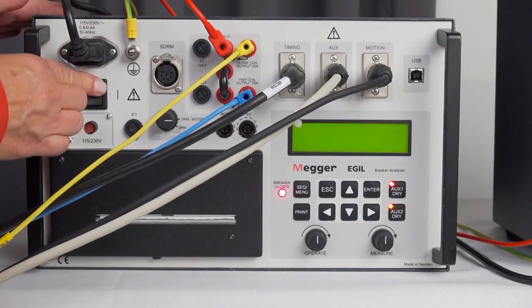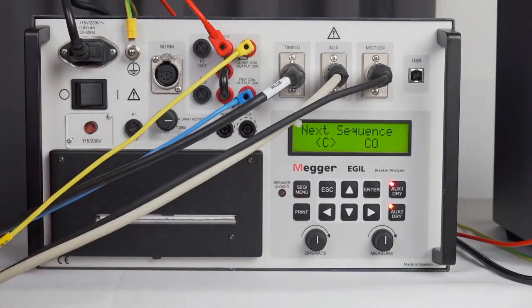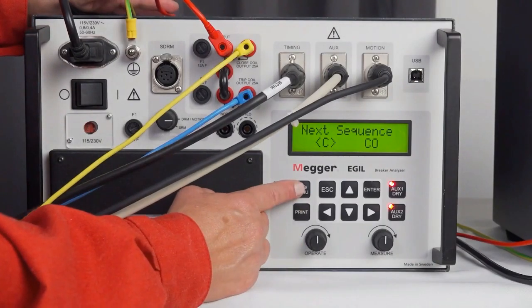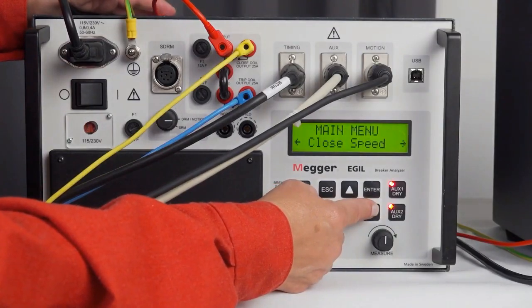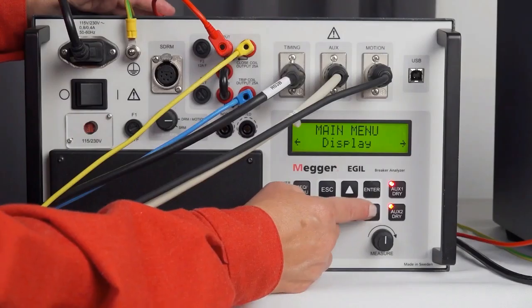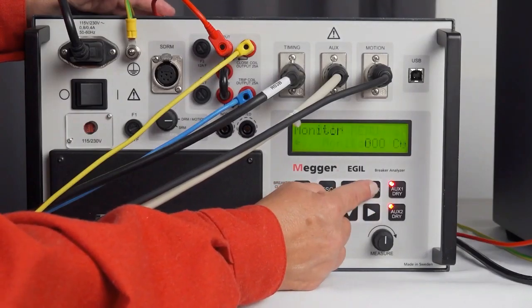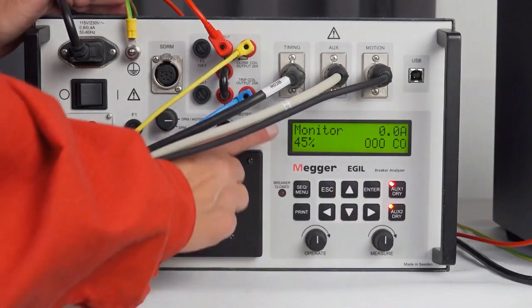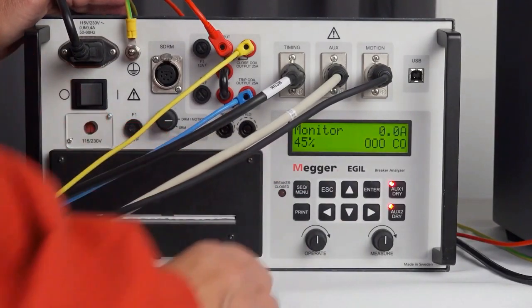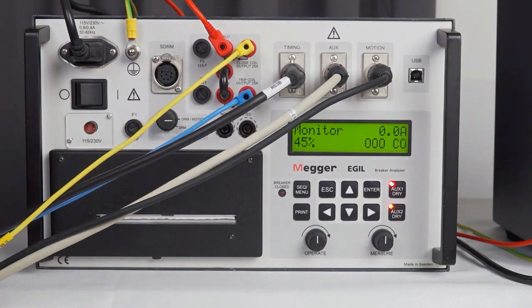I turn on the instrument to check that the transducer is in correct position. I go to Menu and I move to Monitor. Here I can see that the transducer is on 45%. I need it to be between 40 and 60%. And if it's not correct, I need to loosen the flex coupler again and turn the transducer a little bit so it is in this region. That is because the transducer has a gap and we want to avoid that gap during the measurement.